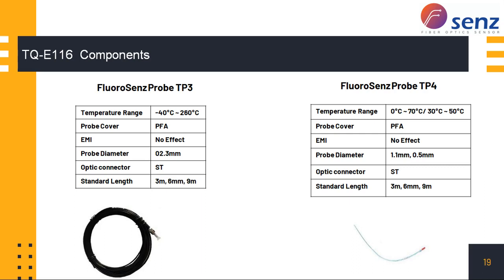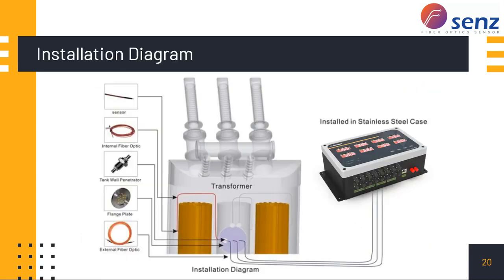So this is in brief about the fluorescence based fiber optic temperature sensors. This is the installation diagram. We install the fiber optic in the different areas of the transformer, and the sensor is brought to the flange plate, where we have the feedthrough for insulating the inside of the transformer oil and the outside. And from outside, the cable goes to our instrument, where all the electronics and the fiber optic sensors are placed. The fiber optic transfers the light, and all the electronics and the sensor are inside this.